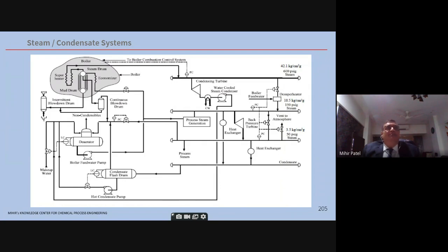This deaerator is a very important equipment. It separates the CO2 and the oxygen from the condensate so that the boiler doesn't see corrosion. You can also dose hydrazine and sodium sulfite, which are the oxygen scavengers. Okay, so this is as far as the steam circuit is concerned.